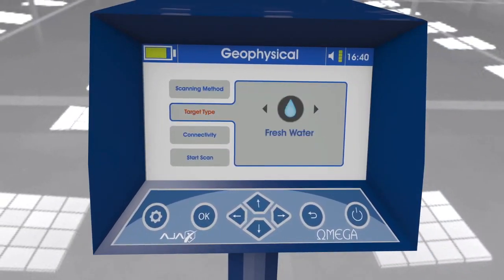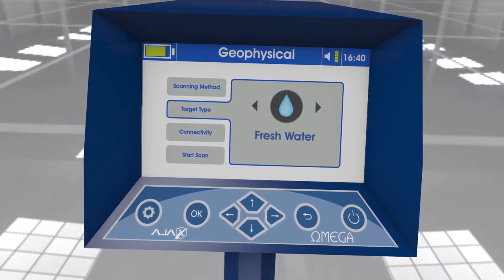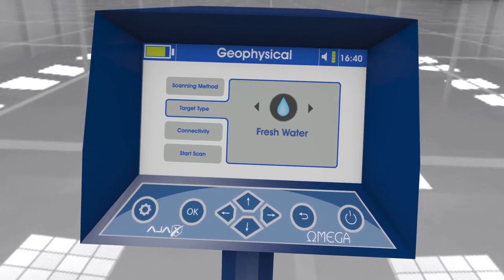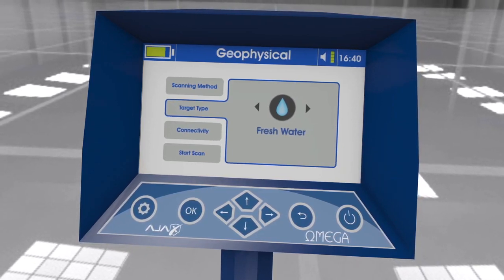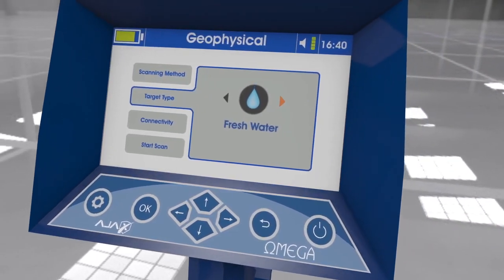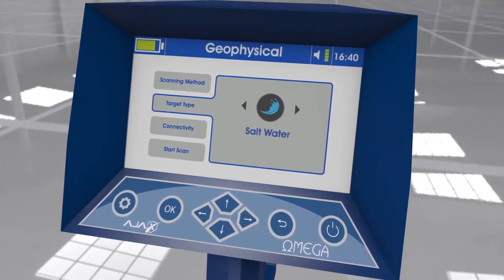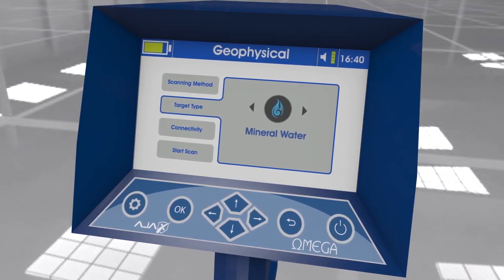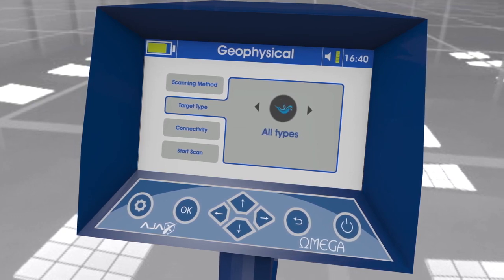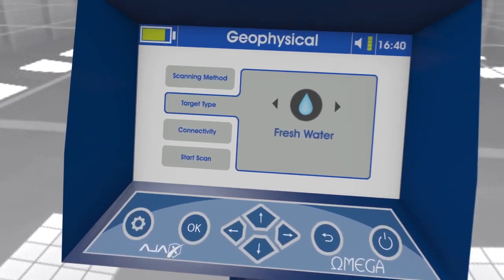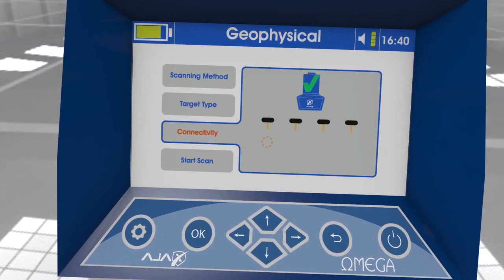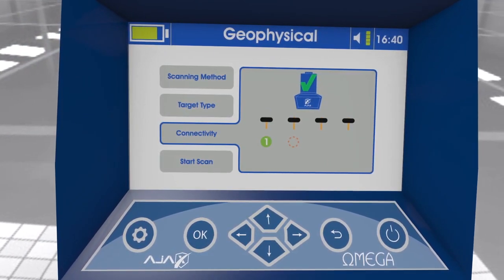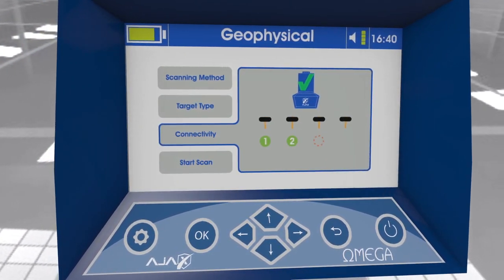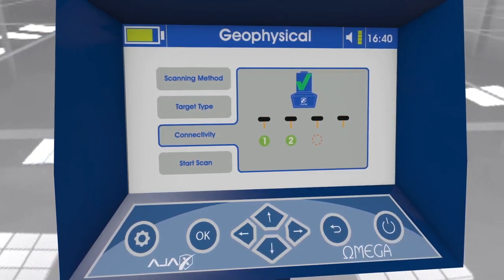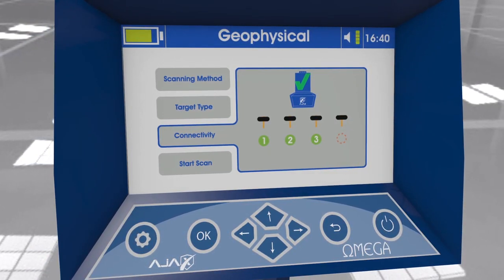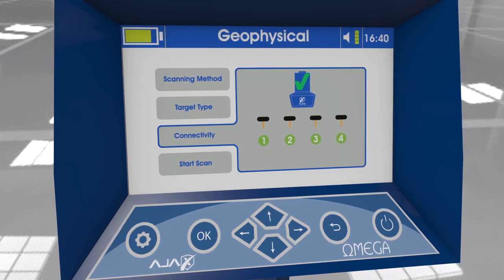2. Target type. There are 4 targets that can be selected by the arrow keys, which are A. Fresh water. B. Salty water. C. Mineral water. D. All types of water. 3. Connectivity. The user should wait for the 4 probes numbers to show inside green circles with a check mark, indicating that the connection between the main unit and the ground scan probes is done successfully.